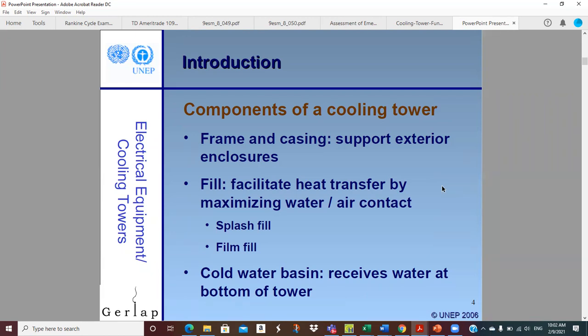And now we have film fill, which is definitely more effective. And this is like the plastic. I think Dr. Languri's got some pieces of fill over in the lab I can bring in and show on the camera here. But it's like PVC stuff, and it's kind of like a honeycomb deal. And a lot goes into designing these fills, especially the film fill. Anyway, the film fill is typically better in most applications these days. And that's a retrofit option, to take an old splash fill tower and retrofit it with film fill, and you get more capacity out of the tower.